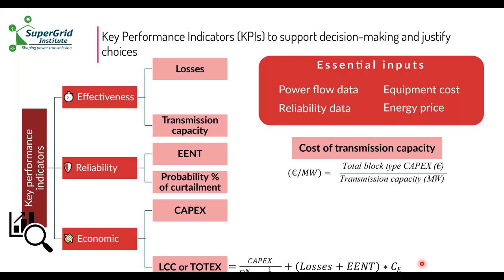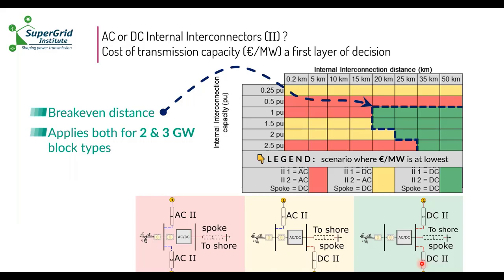To be more concrete, here's an example: a table comparing the three different interconnection types. Whenever the case is red, it shows that the cost of transmission capacity is lower for the pure AC internal interconnector topology of a given block type. Yellow means the hybrid solution is less costly in terms of cost of transmission capacity, and green is for the complete DC solution.